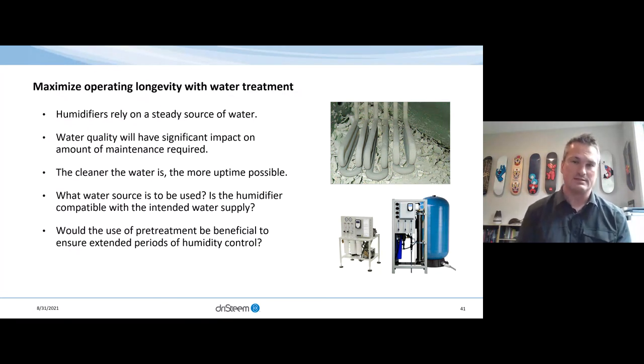For example, if you're using a system with copper heat exchangers, you may not want to use deionized water, as deionized water can be very corrosive to those types of non-316 stainless steel type humidification or heat exchangers. If you're atomizing water or even using evap, you may want to use reverse osmosis water. The idea is if we're using a high pressure system and we're applying this atomized water or atomized vapor in the airstream, we want to remove those minerals because it's the water that evaporates, but the minerals remain.